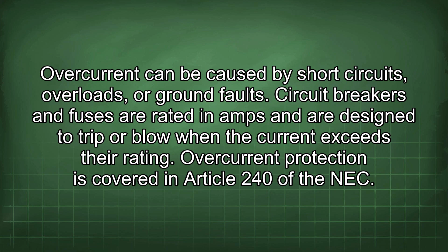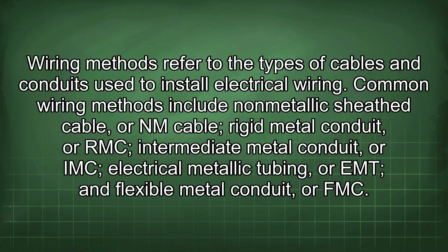Wiring methods refer to the types of cables and conduits used to install electrical wiring. Common wiring methods include non-metallic sheathed cable, or NM cable, rigid metal conduit, or RMC, intermediate metal conduit, or IMC, electrical metallic tubing, or EMT, and flexible metal conduit, or FMC. The choice of wiring method depends on the application, the environment, and the requirements of the NEC. Wiring methods are covered in Chapter 3 of the NEC.